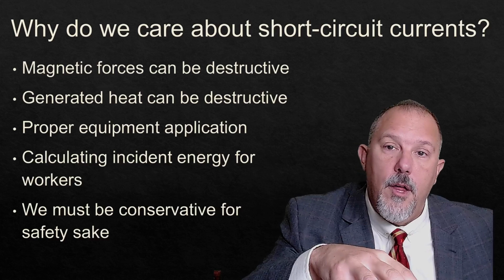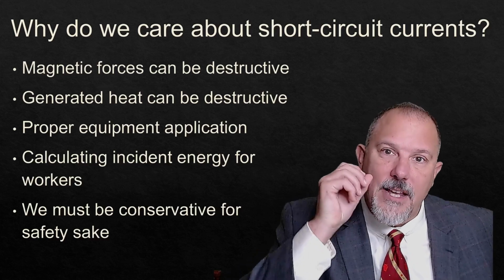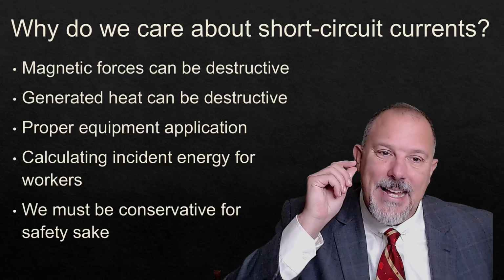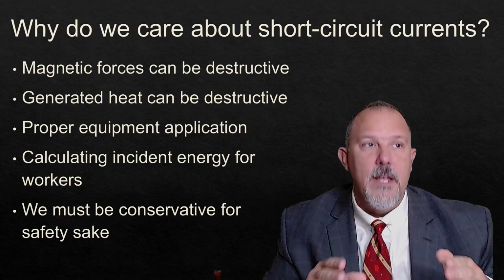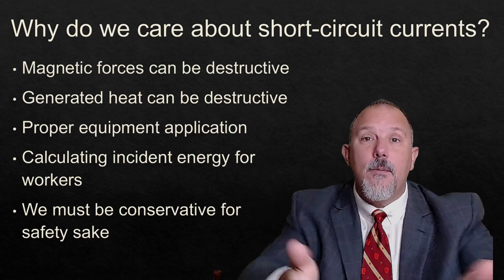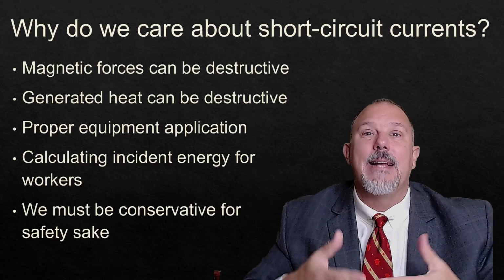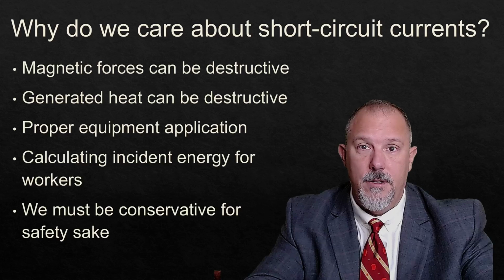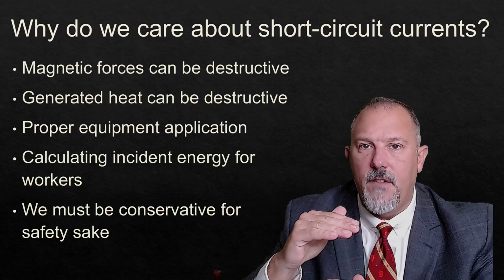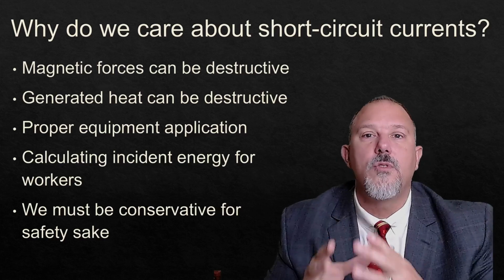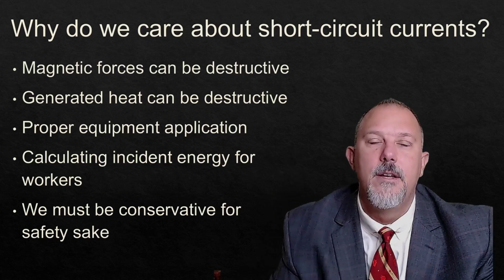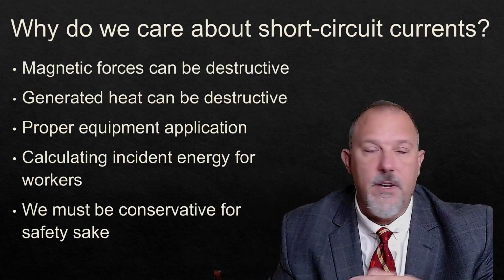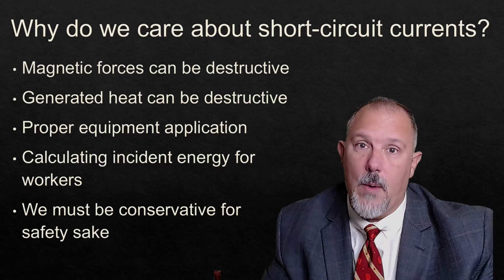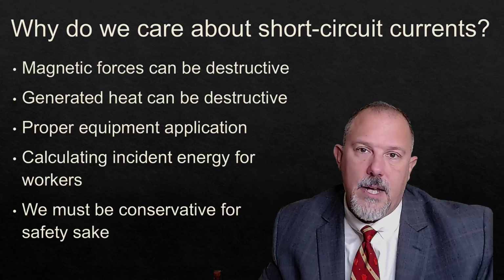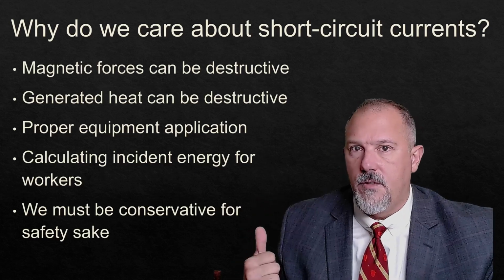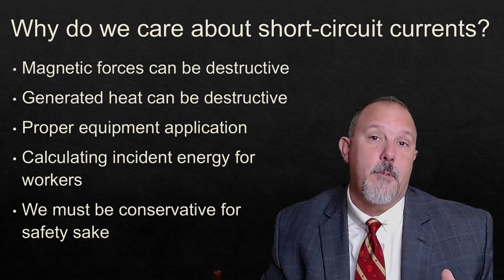You want to know that when a short circuit current is flowing, the equipment that is going to stop the flow of that current can do so. You want to make sure that the equipment that has to carry and deliver that current to wherever it's going, for as long as it will be permitted to flow by the overcurrent protective device, holds it together under the pressures of the magnetic forces of that current. So if I have an industrial control panel that's delivering fault current, if I have busway that is delivering that current for, say, 2-3 cycles, based upon the clearing time of the overcurrent protective device, the equipment has to hold it together under the pressures of those magnetic forces.